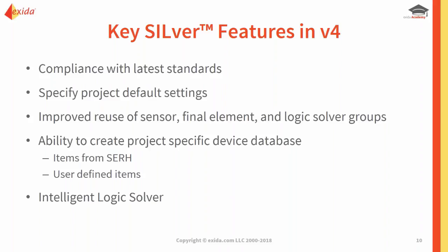There's an improved ability of reusing sensors, final elements and logic solvers. You're able to create a project-specific device database. So as you are modeling your safety functions, you're going to select equipment out of our equipment database, the Safety Equipment Reliability Handbook, or you're going to define your own data, and all those items are embedded in a device database that will allow you to easily select from in subsequent SIFs.